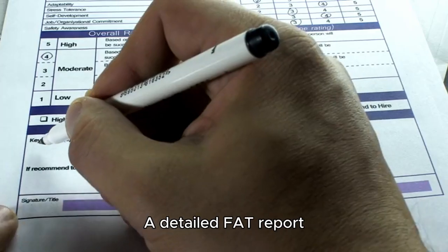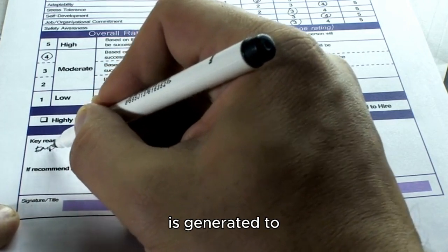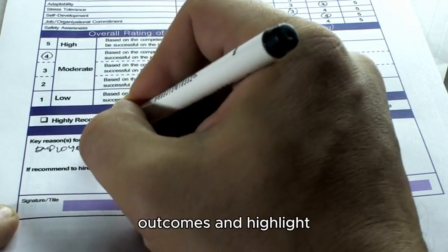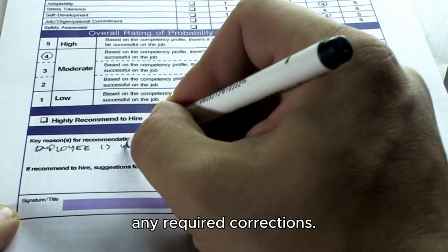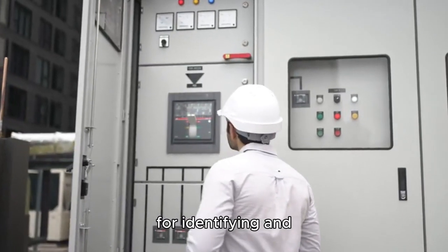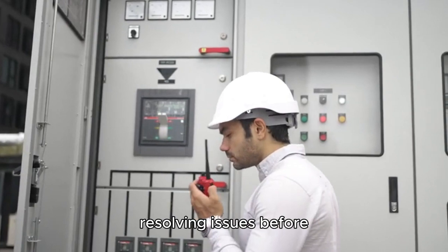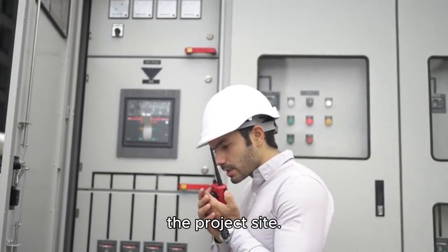This includes testing protection relays, communication protocols, control logic, and interlock functions. A detailed FAT report is generated to document the test outcomes and highlight any required corrections. This phase is invaluable for identifying and resolving issues before the switchgear reaches the project site.